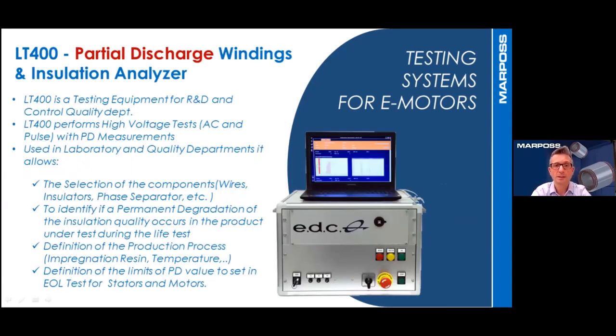LT400 is an equipment designed for testing in lab and quality control departments that performs high voltage tests, AC and pulse, with partial discharge measurement. Used in lab or quality department, it allows an analysis for selection of the best components, like wires, insulators, phase separators, and so on, to identify after how many hours of life test a permanent degradation of the insulation quality occurs in the product under test.